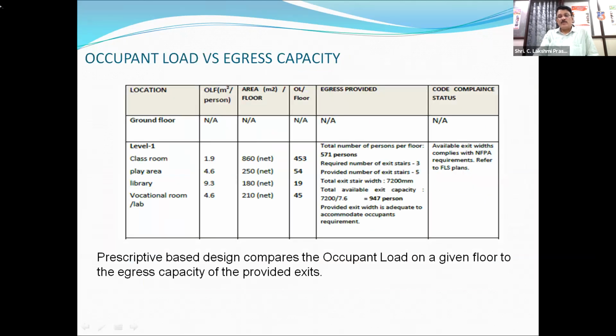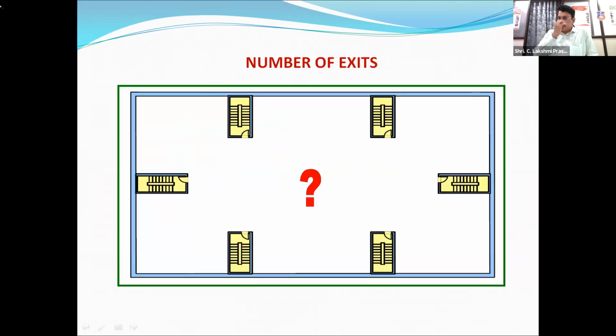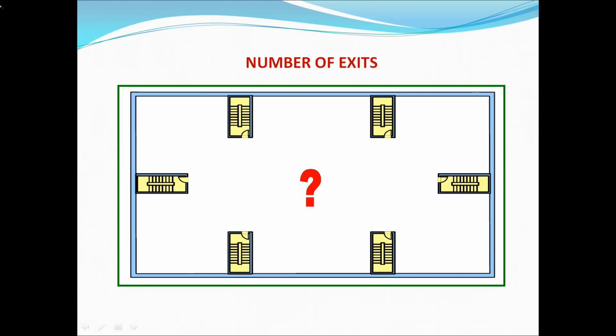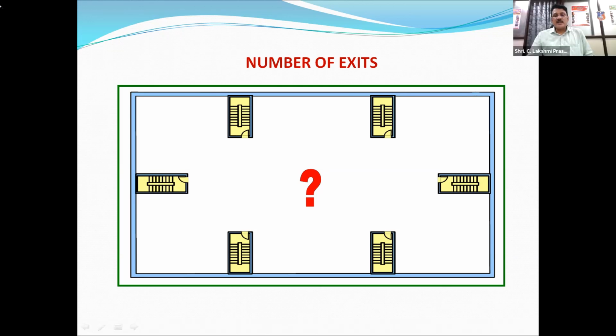Generally, an important principle is that the staircases have to be staggered in the building. They should not be just side by side, for various reasons. Because if one staircase becomes unusable, the other staircase should be available for people to escape from the building. So the staircase location is a very, very important design concept to keep in mind.